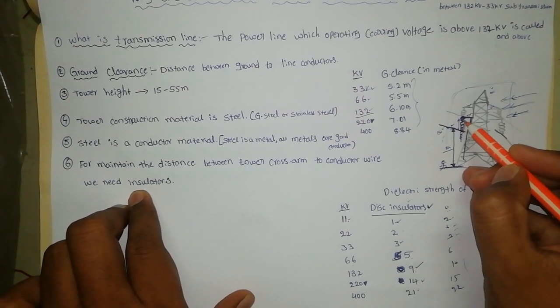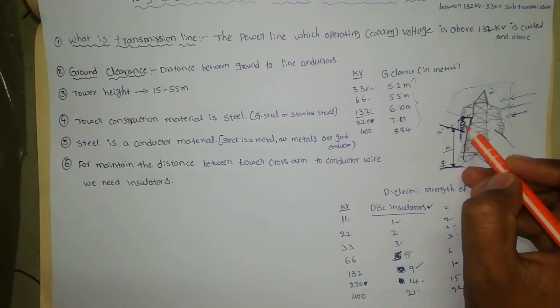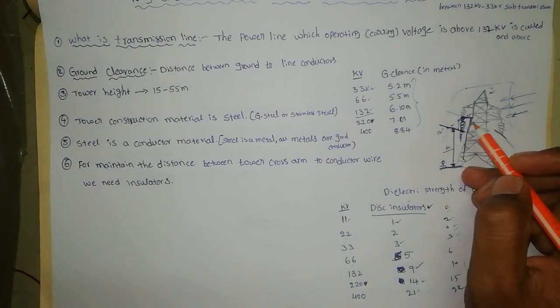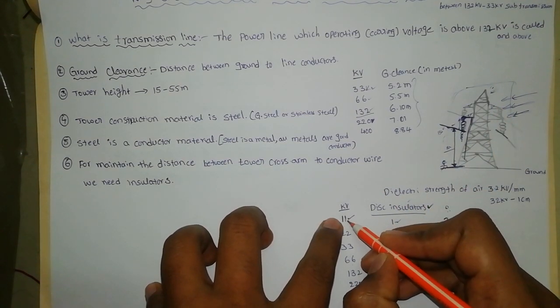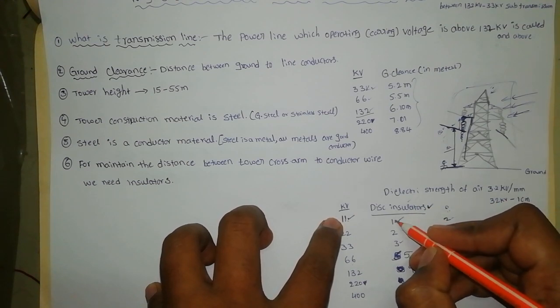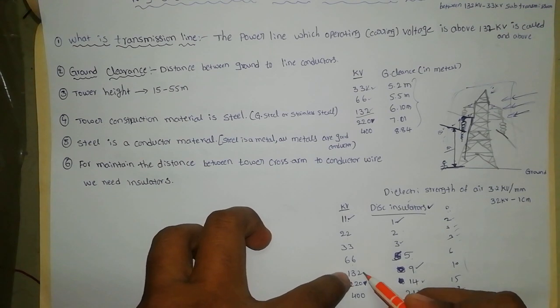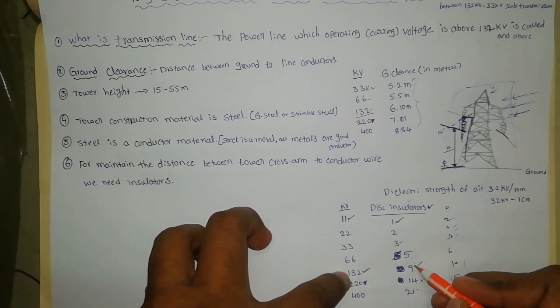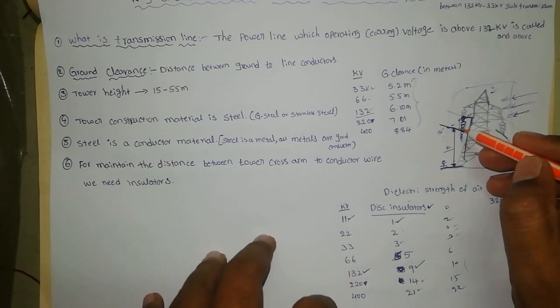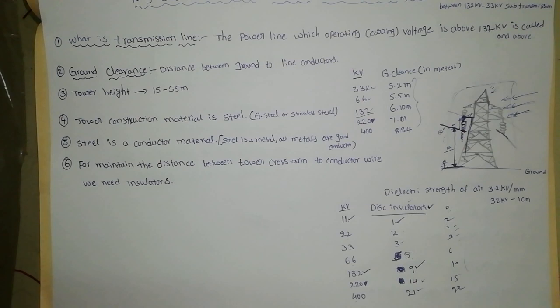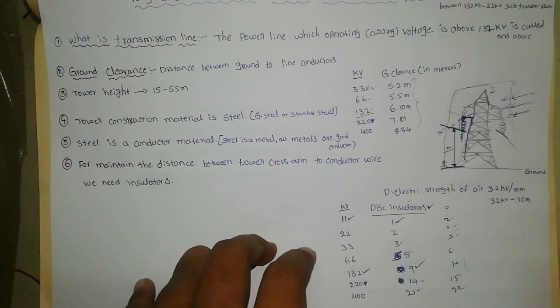We use disc insulators for this purpose. If the operating voltage is 11 kV, you need only one disc. For 400 kV, you need 21 discs. These insulators hold the conductors, while steel provides the strength as the preferred structural material.